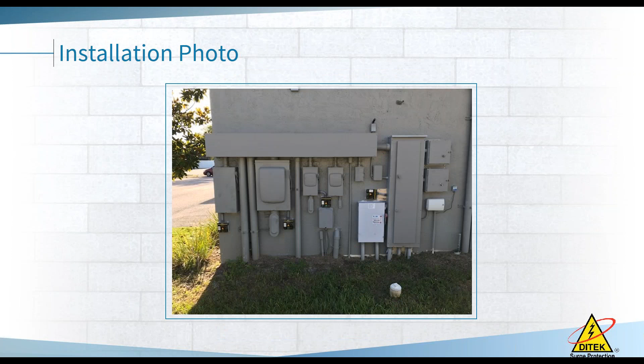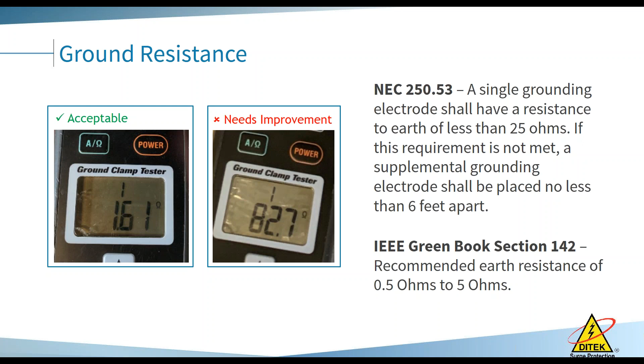Grounding and bonding, I'm going to spend some time on this because it's important as well. NEC code, 25 ohms maximum. The IEEE standard is less than 5 ohms. That's what we follow and we encourage our customers to adhere to. This is how we test when we're on the field.